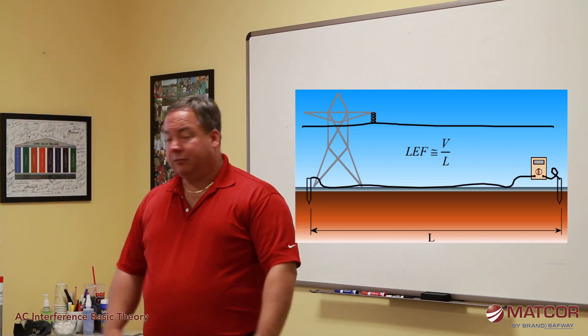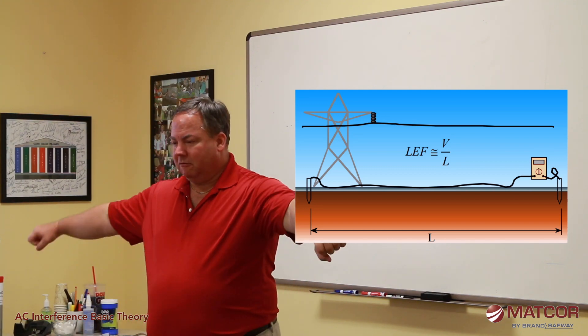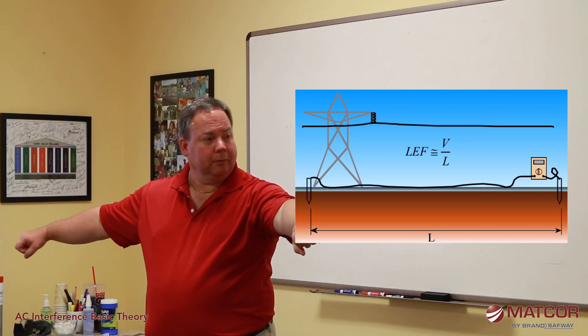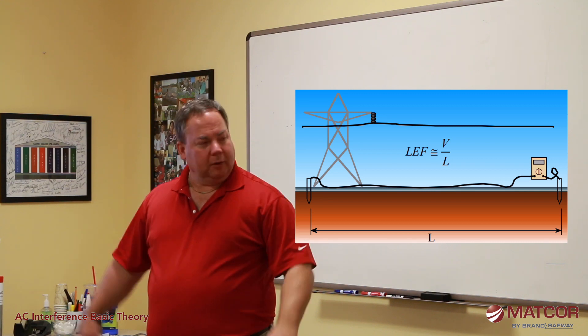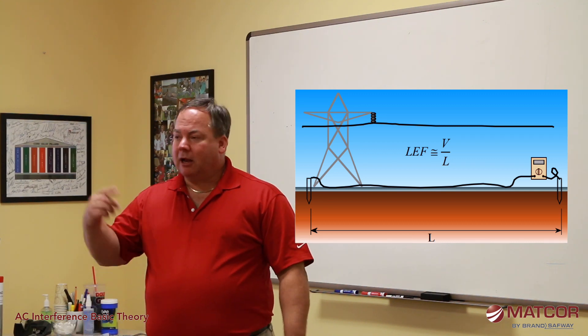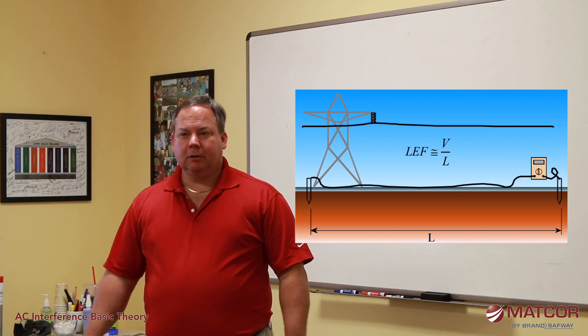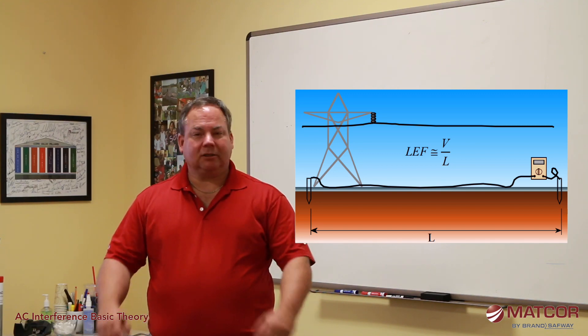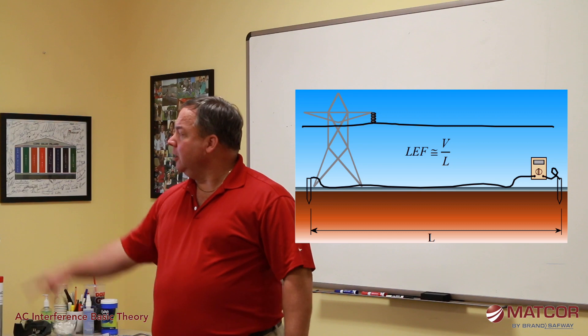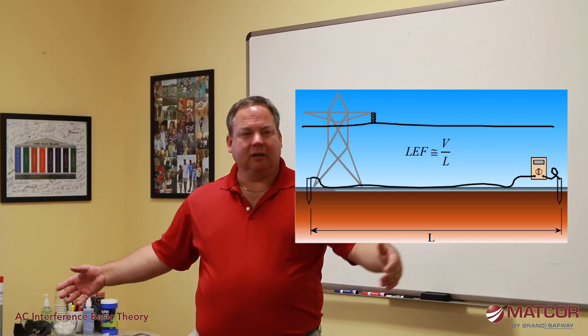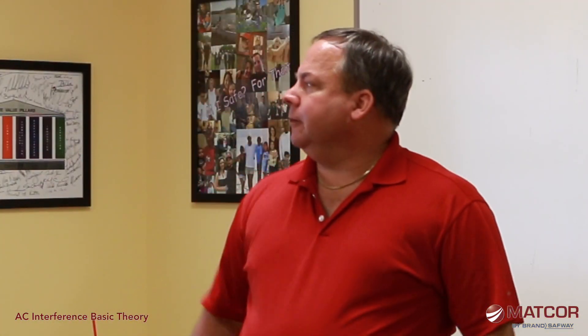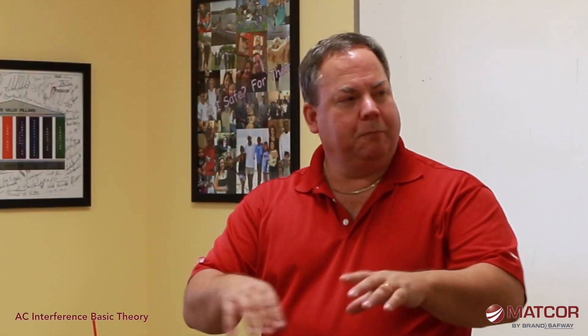Being in that field will cause the pipeline to inductively pick up current. We call this an LEF field — longitudinal electrical field. You can actually measure it. If you were to take a piece of bare copper cable, put two pins in the ground, put that copper cable between them and stake it, that copper cable will start to pick up current. Depending on how long the co-location is and other variables, you can actually measure the voltage picked up over a certain length of cable.